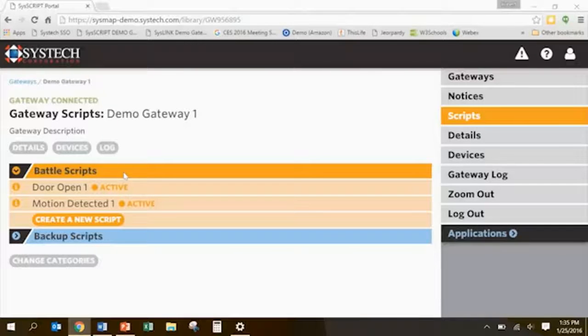Essentially, when the door opens, we start a timer that counts down. If there's no motion in the room after the door closes, after a period of time the HVAC system turns off. But if there is motion after the door opens and closes, the HVAC system stays on. That's why we need a sophisticated script - this is a real commercial application, not just a simple algorithm.